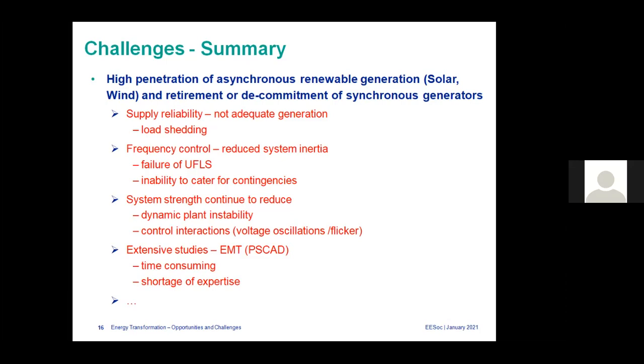And another issue with asynchronous generation is we know they don't contribute much fault level or system strength to the system. So having high penetration of asynchronous generation means you have continuing reduction of system strength. That could lead to dynamic plant instability and also control interactions, as we discussed, which could lead to flicker issues. And all these things lead to more extensive studies, mainly these days PSCAD modeling. And if you have used PSCAD, they use very small time steps, often microsecond kind of time steps, 6 microseconds, 10 microseconds. So it is very time consuming to do a simulation.